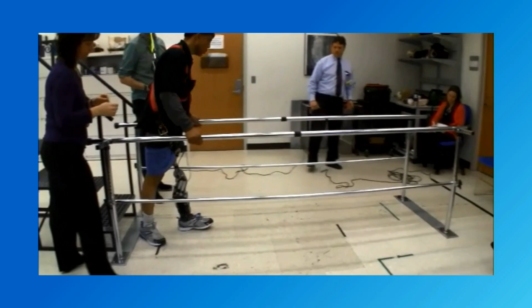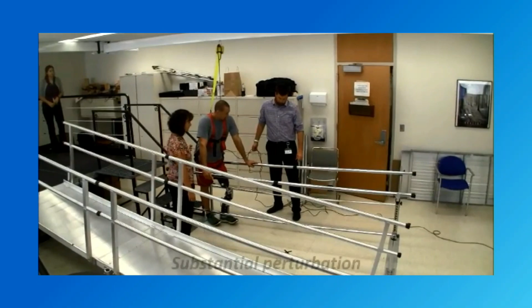Do you have a question, Blue? Yeah, does the system take into account user adaptation and also changes in the muscle physiology as the musculature changes? It does. So some of the systems we have implemented use EMG, some of them don't. Our philosophy is it has to work really well without any EMG at all, just using onboard sensing. Then we have a two-stage system, where one expert is the non-EMG system, and a second expert is the EMG system. We are always trying to predict things in real time, but after they happen, we can measure what actually happened and compare it to our prediction. If what actually happened was the same as what we predicted, then we can do a small update to the controller. So it gets smarter as people walk, but there is a risk that it will diverge as well. So we have to be really careful in the gains that we put on those controllers.